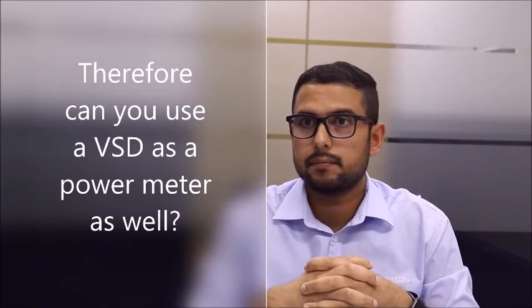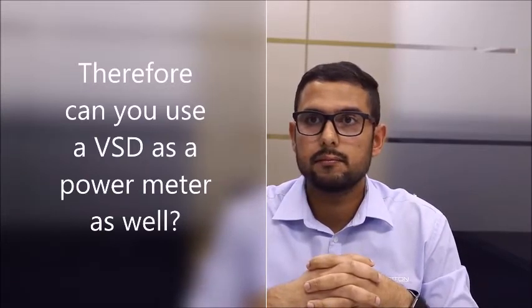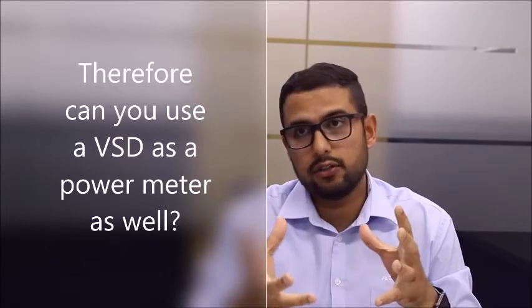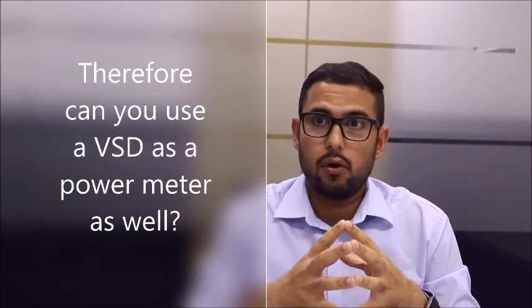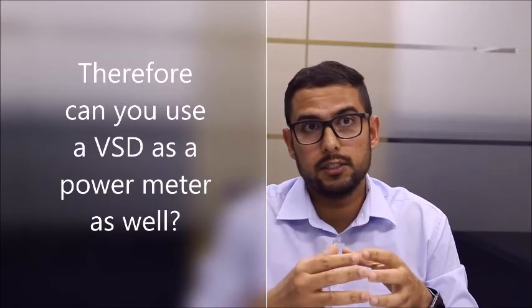So the DDC can read the kilowatt hour consumption? Yes, it can. It's got a set of registers. We call them points or registers. It's got a set of points that we get from the manufacturer, and when we connect via high level, we fix up our communications with it, and we can read all those values out of it. Can you use the VSD also as a power meter instead of having a power and energy meter installed? You can, yes, just for monitoring purposes and for your building tuning purposes. But if you need to do billing based on the power consumption, you cannot use data from the VSD.